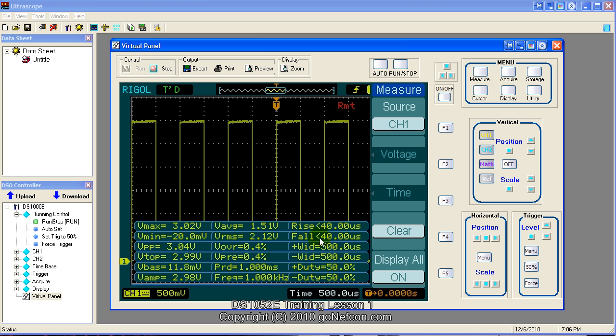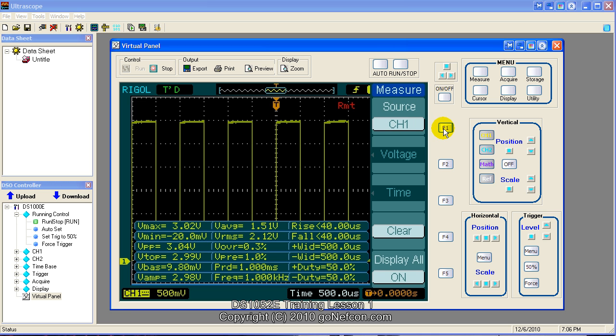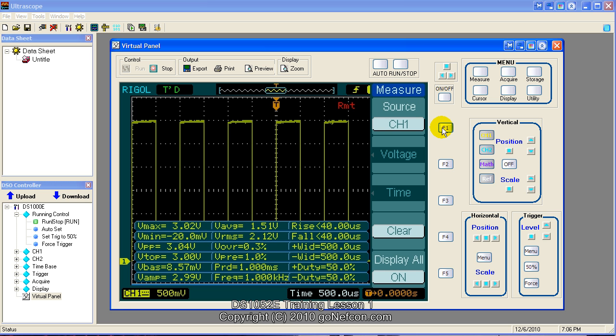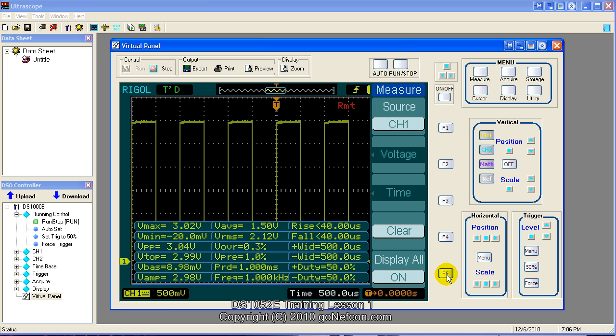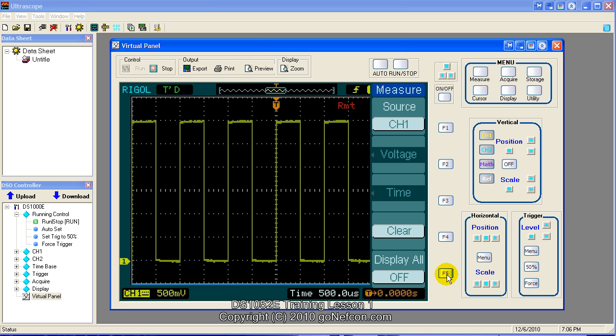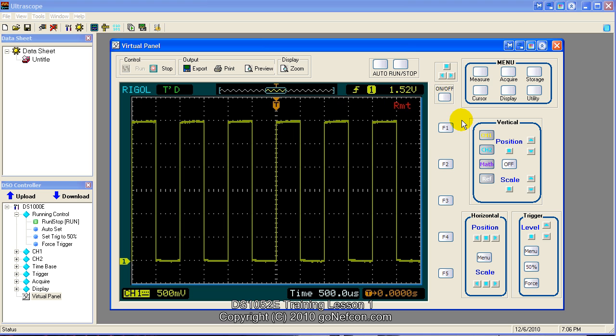And the signal is on channel one because that's what our source channel is for the measurement function. You could change your source channel to channel two. But in this case, there would be nothing because there's no probe connected to channel two. So just make sure your source channel and your measurement function represents the channel that you wish to measure. So we'll turn this off. Measurement results turned off now. And we'll click the measurement menu button. That'll clear the measure menu.